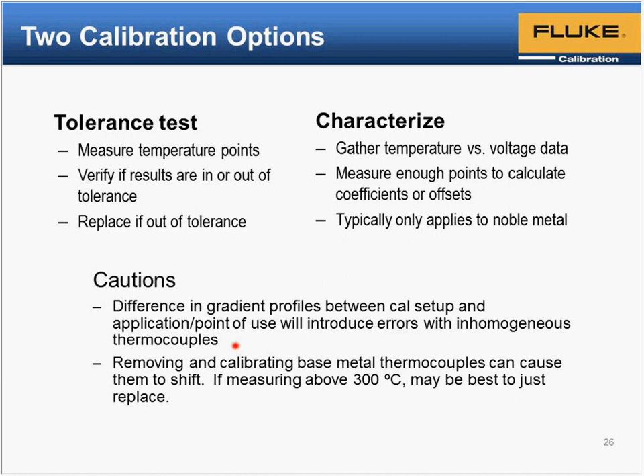And so what's important, if you do calibrate thermocouples, is to describe in the calibration report where the gradient region is located in the instrumentation you used for calibrating the thermocouple, and decide if that is consistent with the application. To summarize, think of it this way: if the gradient region in the calibration process is 20 centimeters from the tip of the thermocouple, but when you put the thermocouple inside a furnace the gradient is 30 centimeters away from the tip, you're using a different section of the wire than you calibrated in the lab. That's why it gets all crazy when you start trying to drill down on sources of uncertainty with thermocouples.